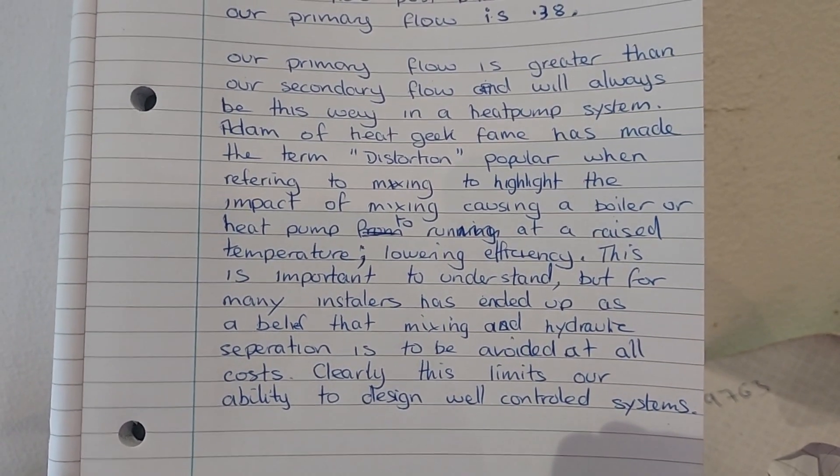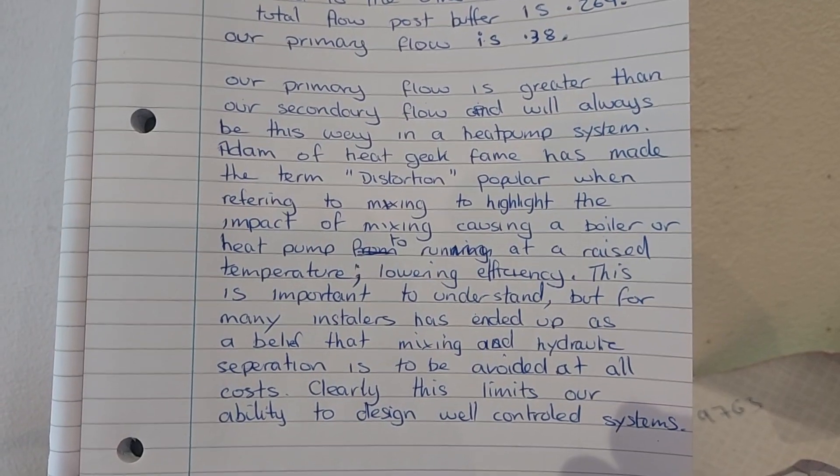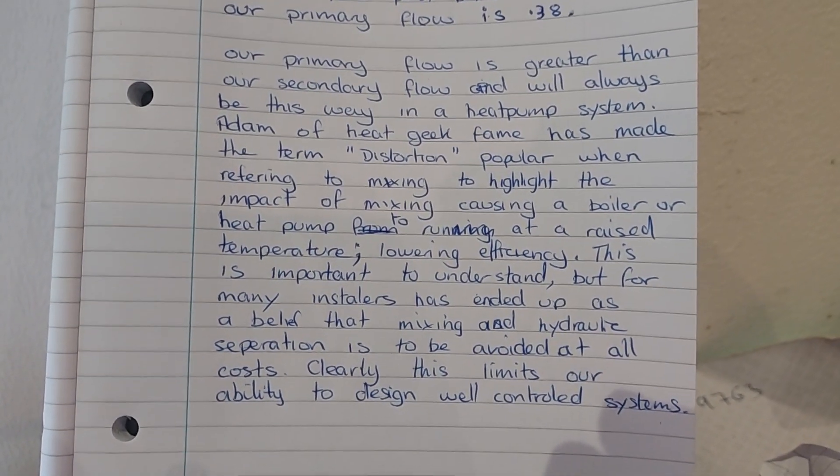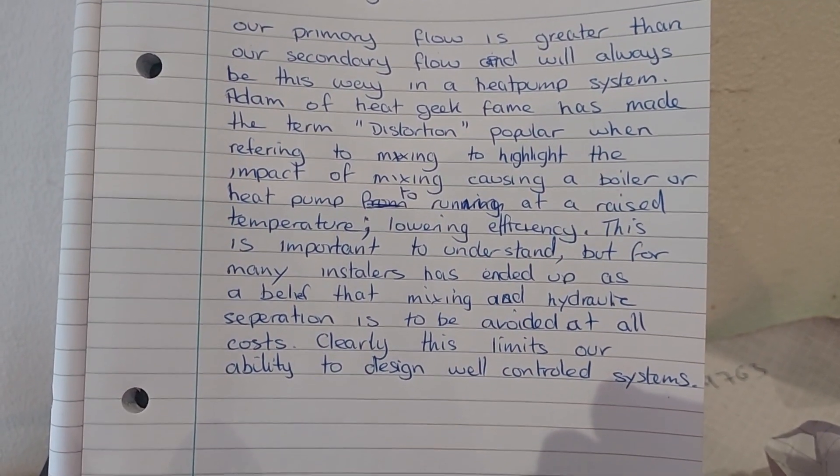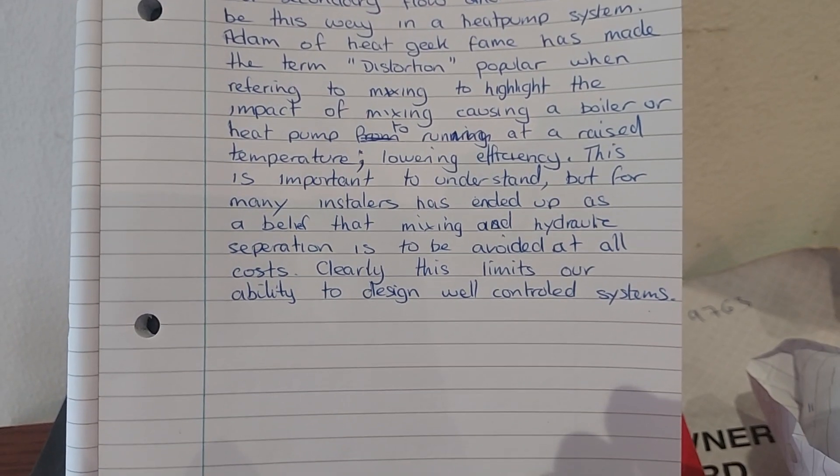Adam of HeatGeek fame has made the term distortion popular when referring to mixing to highlight the impact of mixing causing a boiler or heat pump to run at a raised temperature, lowering efficiency. This is important to understand, but for many installers has ended up as a belief that mixing and hydraulic separation is to be avoided at all costs. Clearly, this limits our ability to design well-controlled systems. We really need to keep on top of understanding how mixing and certain design techniques affect our design outcomes. It's going to be advantageous when fitting or retrofitting a heat pump onto a system that has both radiators and underfloor heating to be able to run these at different temperatures. I think a lot of people haven't done the calculation and they just assume they're going to get negative distortion and they're going to be sending the efficiency of their heat pump down the toilet, basically. And this isn't the case.